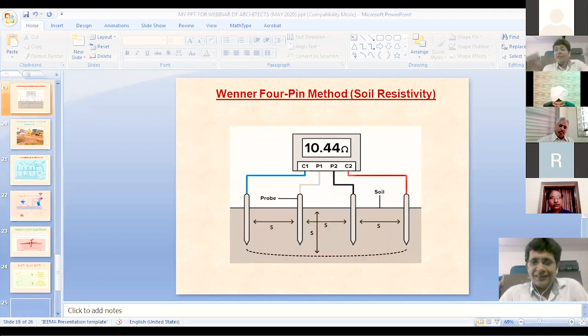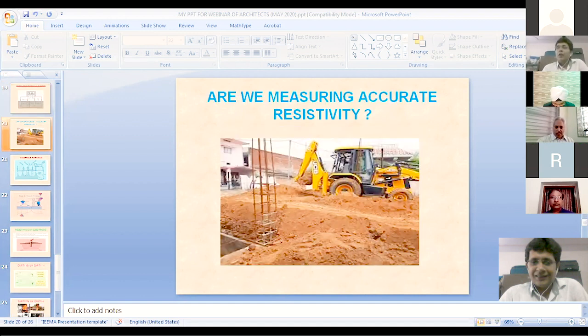This is how we measure earth resistivity at site. But the problem is this: you are measuring the resistivity of the top 5 or 6 meters, but you never know the resistivity beneath that. Most of the time at projects, refilling is required, filling soil or sand to raise the level. When you fill with good resistivity, good quality soil, it helps you. In case the quality is not good, it doesn't help, it makes your design weak, and you are playing with the safety of people in that vicinity, in buildings or projects.